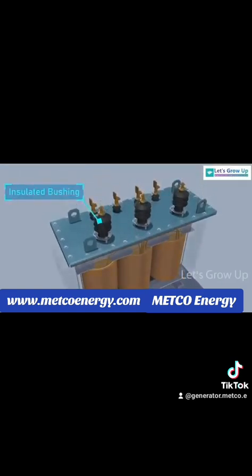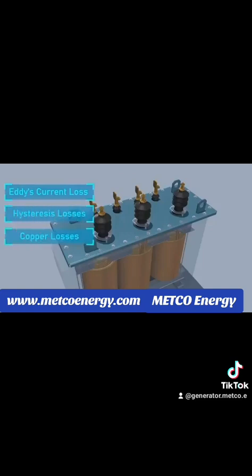During its working, or transferring the power from the primary to the secondary winding, various energy losses happen. Like eddy current losses, hysteresis losses, and copper losses. All these losses generate heat. To prevent heat, transformer oil is used inside the tank. The main role of transformer oil is to act as a coolant and to insulate. Transformer oil is an exceptional heat conductor, and can effectively reduce the copper coil's temperature, stopping them from burning.